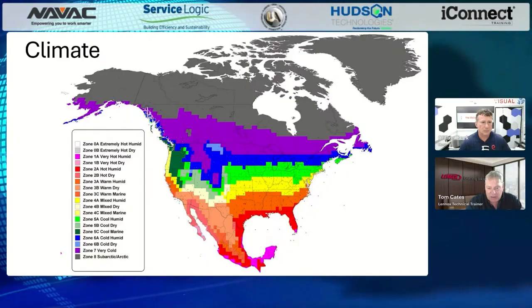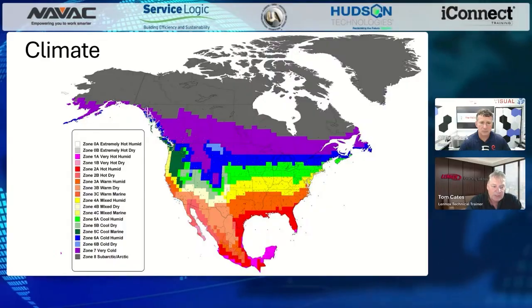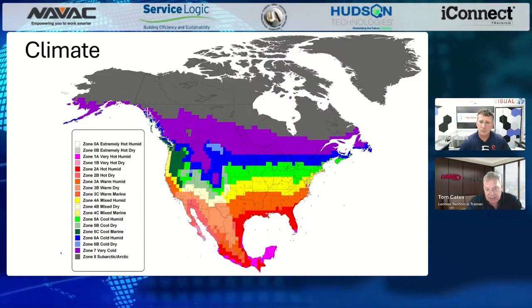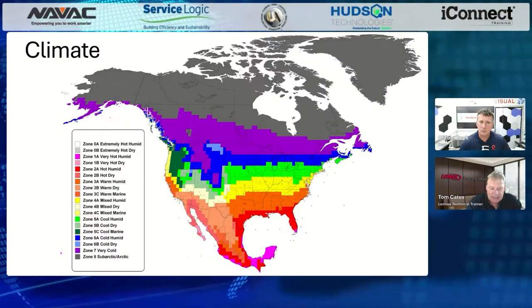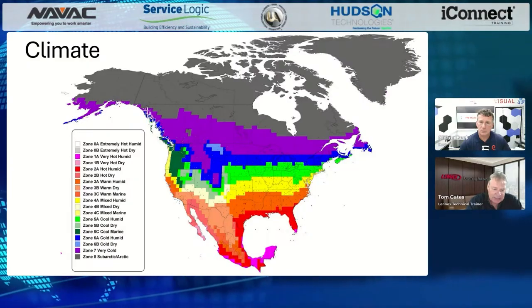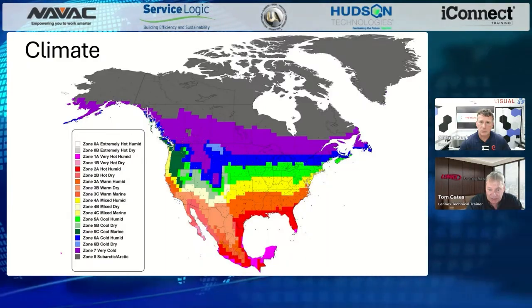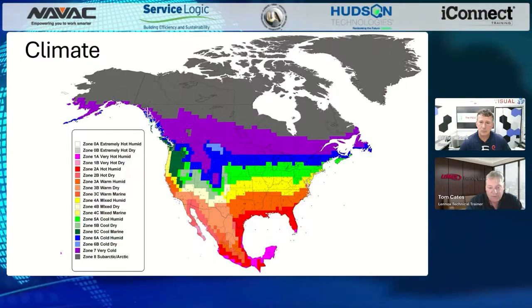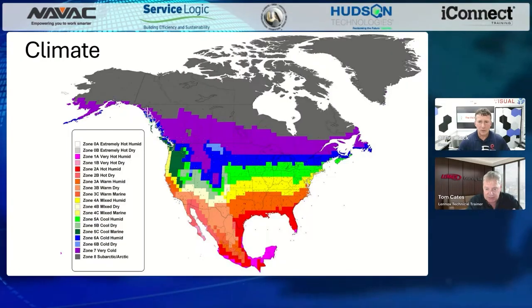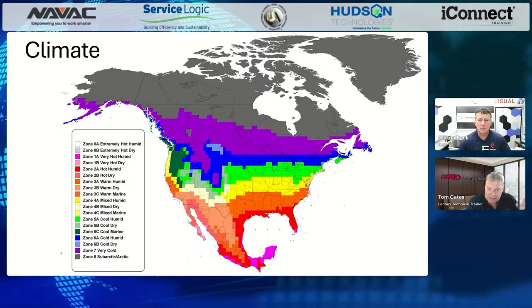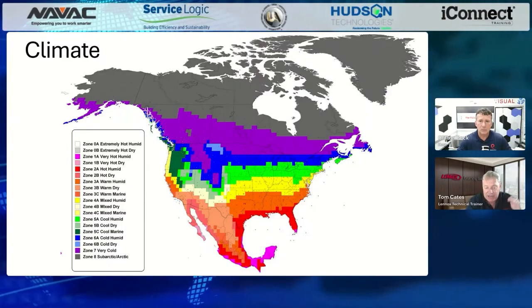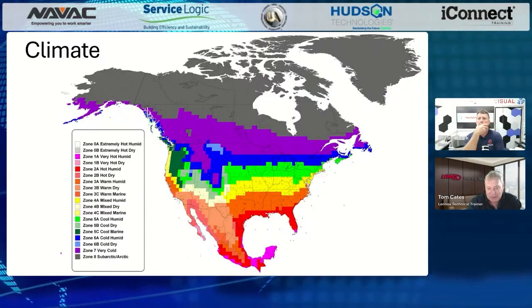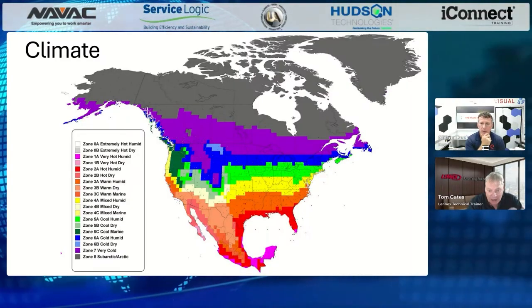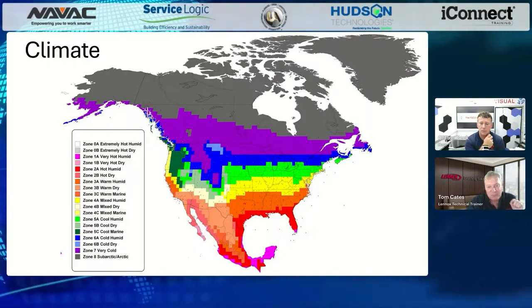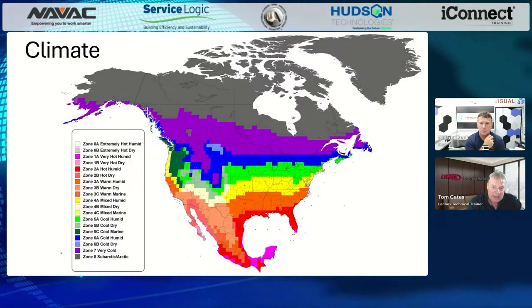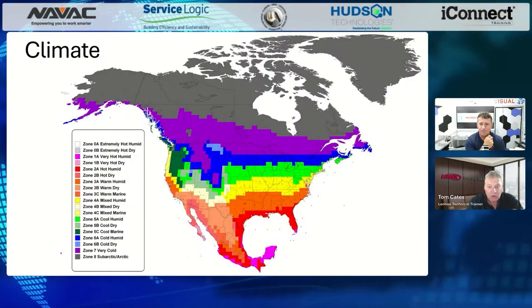When they first came out, it was generally assumed that an HRV would be used in a cold climate and an ERV would be used in a warm climate. That is starting to change pretty significantly, actually, Clifton. We're starting to see ERVs as a more viable option even in colder climates today, for two reasons: one, we were oversizing our ventilation systems to begin with, and actually reducing relative humidity in homes to an uncomfortable point. ERVs actually do a better job of maintaining relative humidity, as opposed to reducing it, in a cold climate zone.